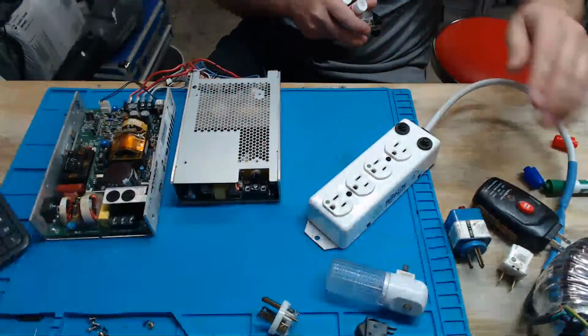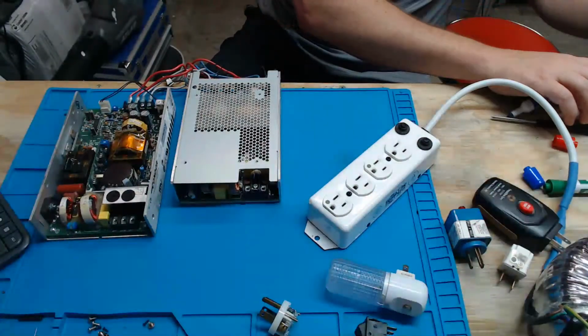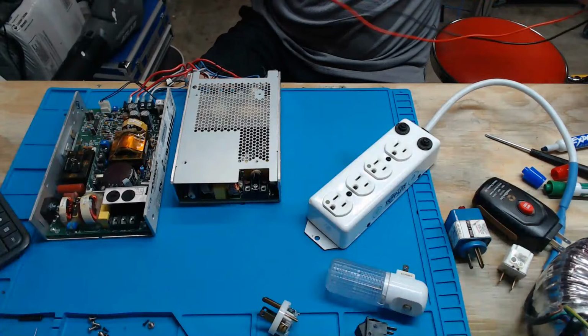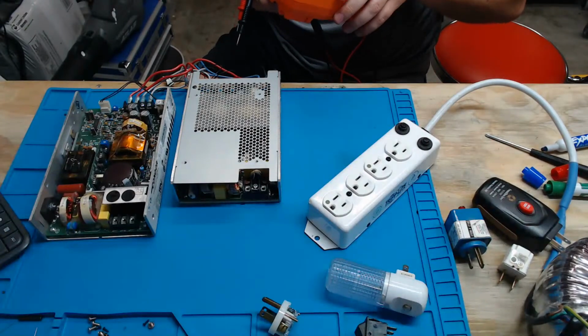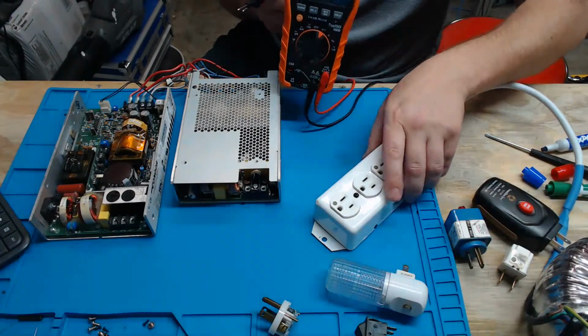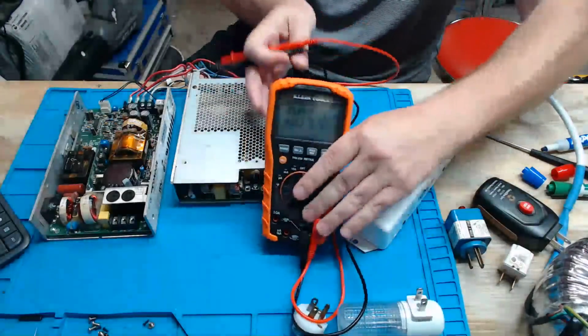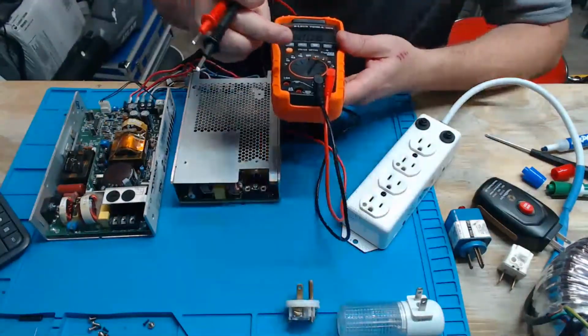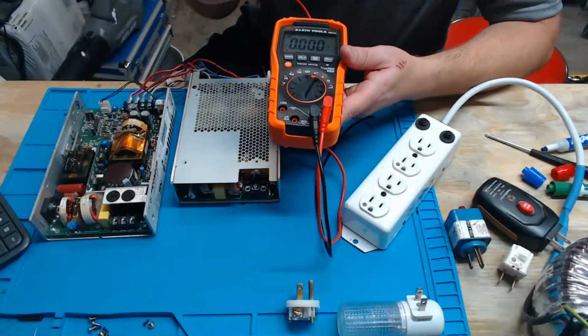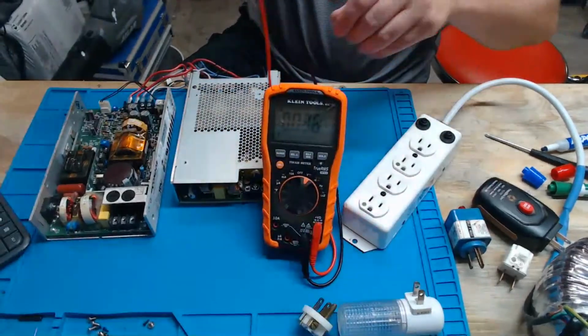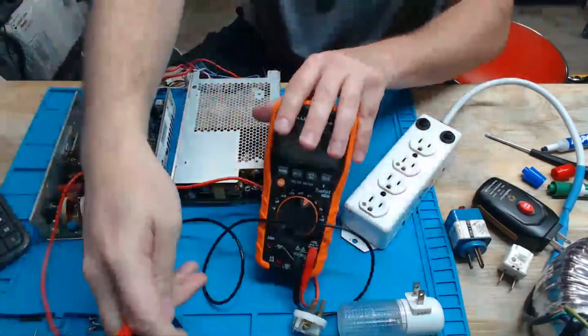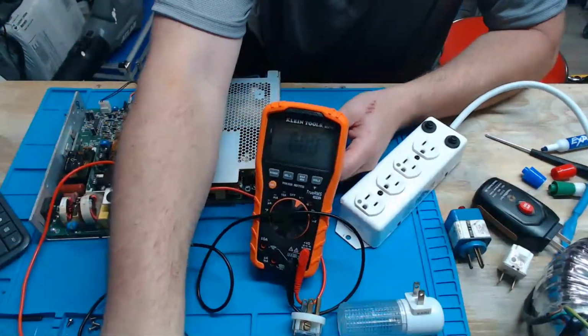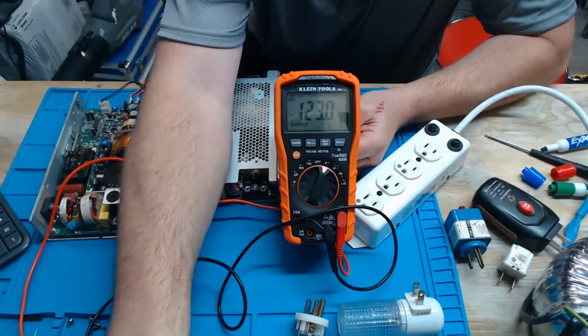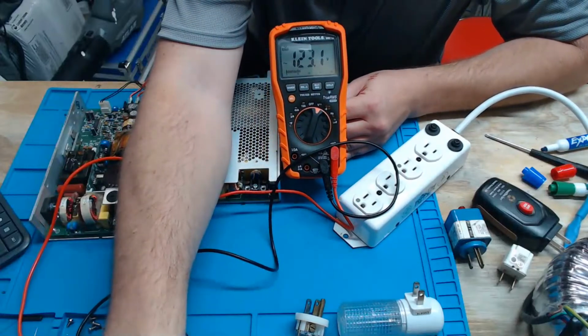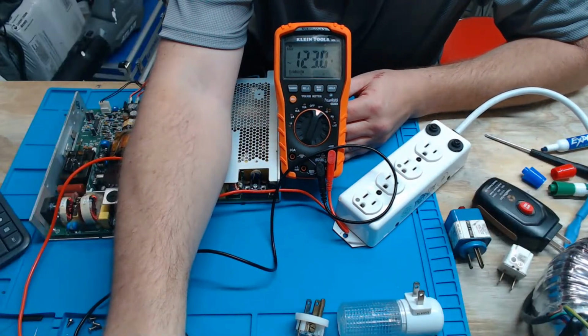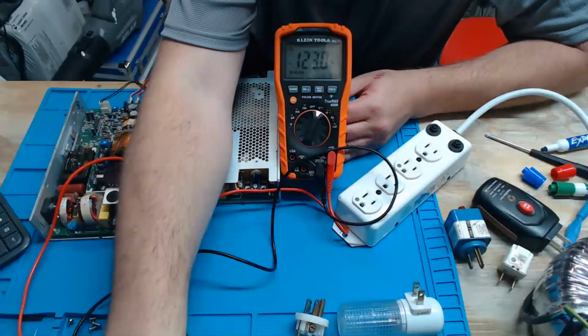This guy right here. You can see my little transformer up to the side. Now, in a normal device, let's see, can I get this so that y'all can see it? Yes, absolutely. From voltage, AC. So in a normal device, if I go from line to neutral, you can see right there, I got 123 volts. I know it's reversed. Can't do anything about that at this time.